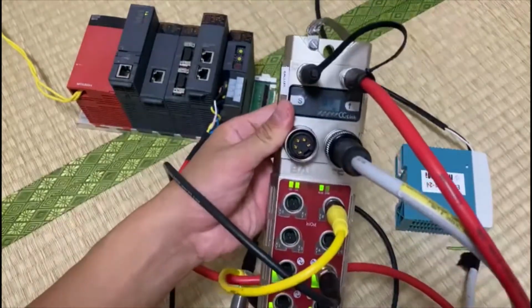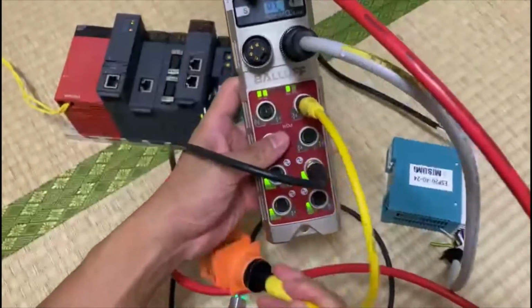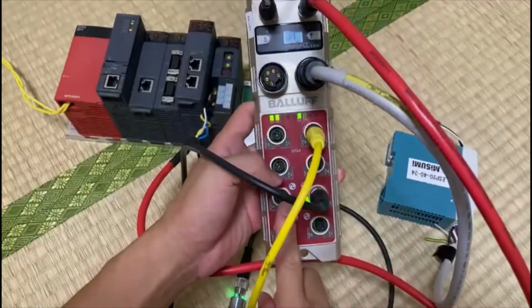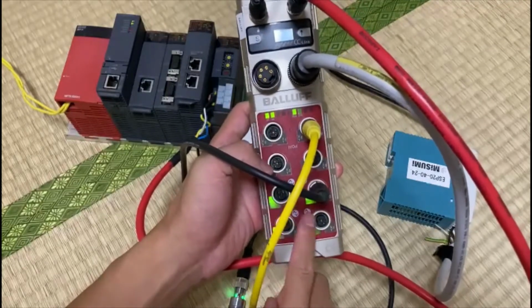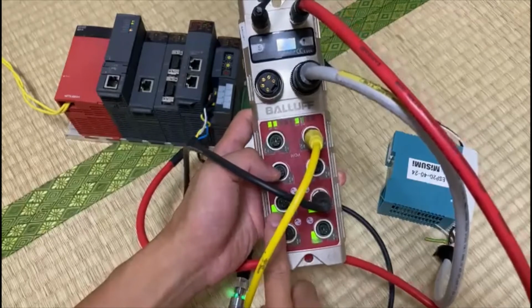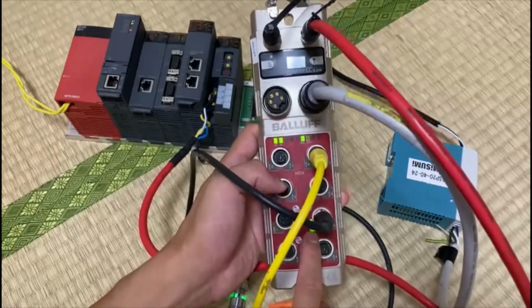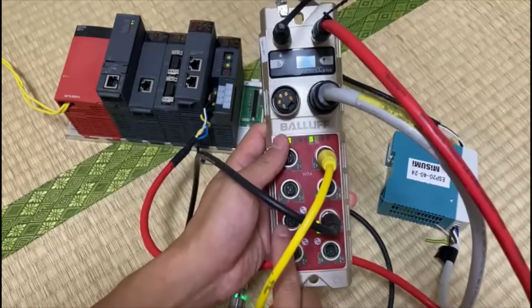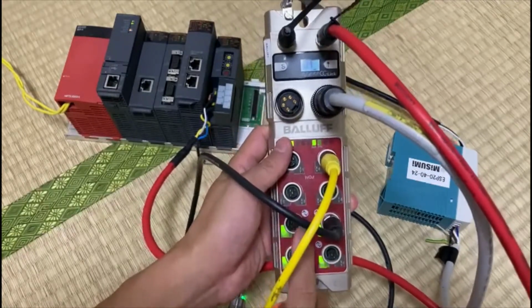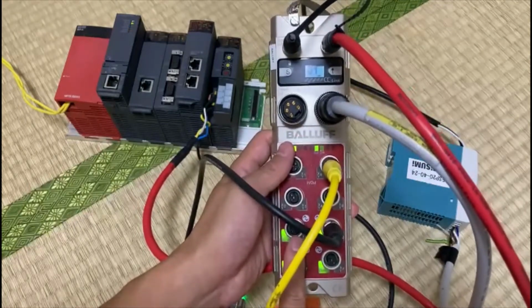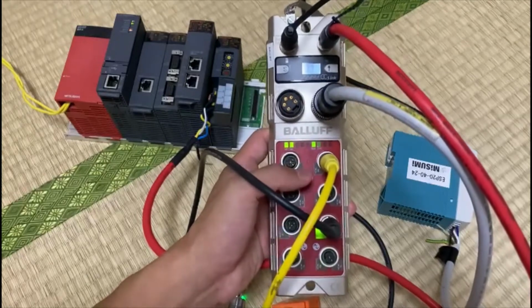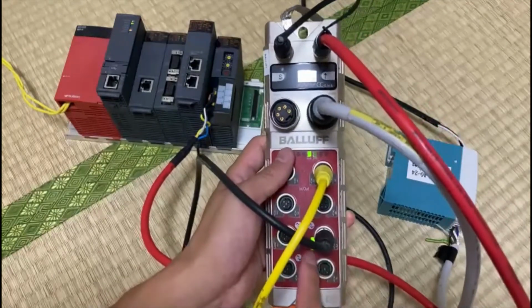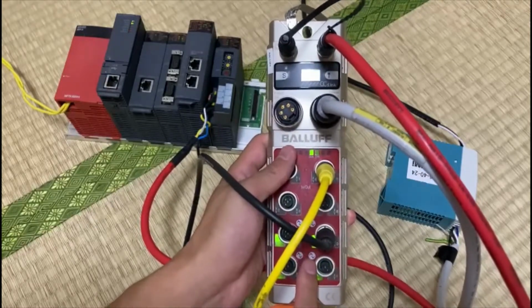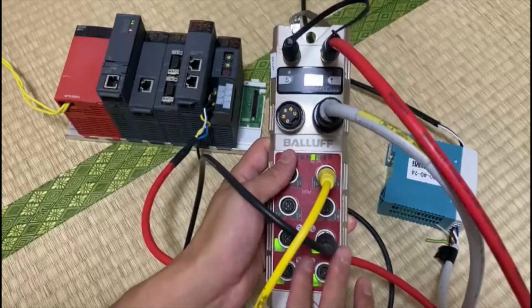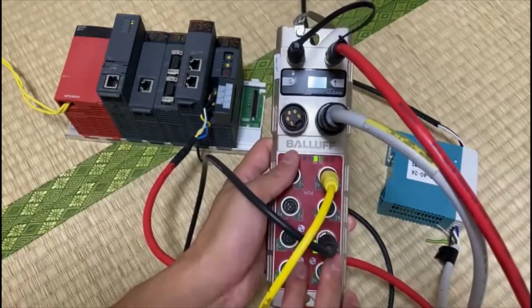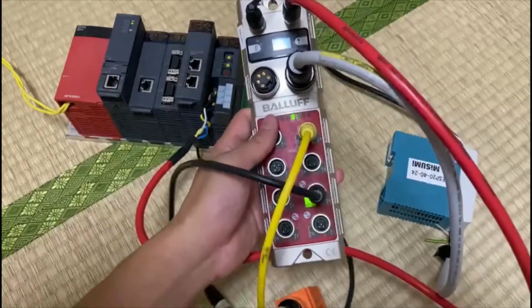Okay, and here you see I'm connecting an input sensor. Here you see four LEDs in green color, and this port is flashing in green, and this one is turned on. What does it mean? If this lamp is flashing in green, it means this port is configured as an IO-Link port, but no IO-Link sensor is connected, or the IO-Link sensor has some problem. And here, the green LED is turned on. It means this port is configured as an IO-Link port, and also communicating with the IO-Link sensor.